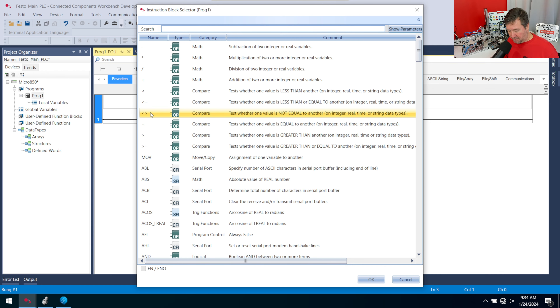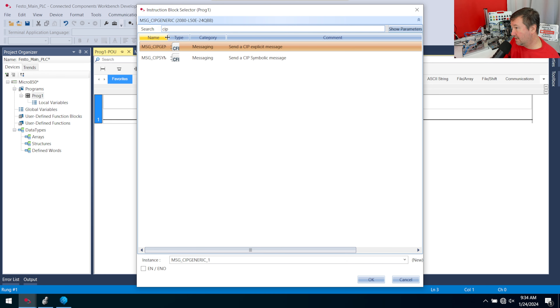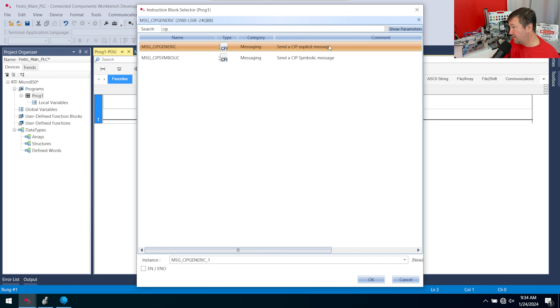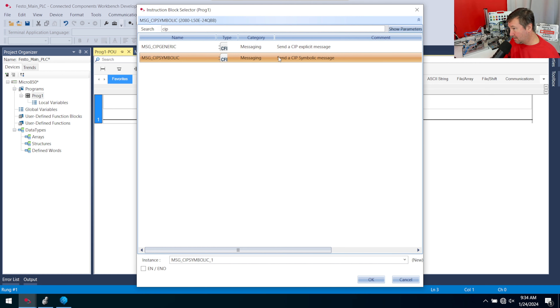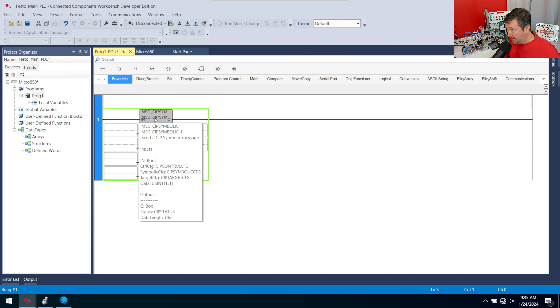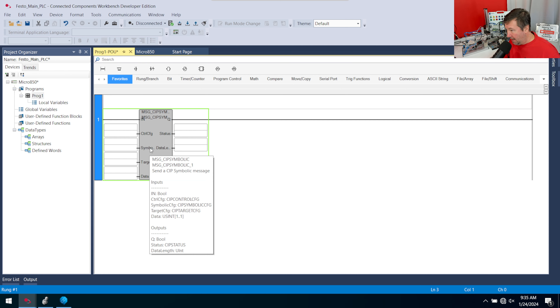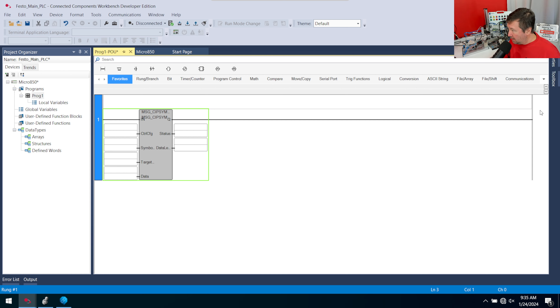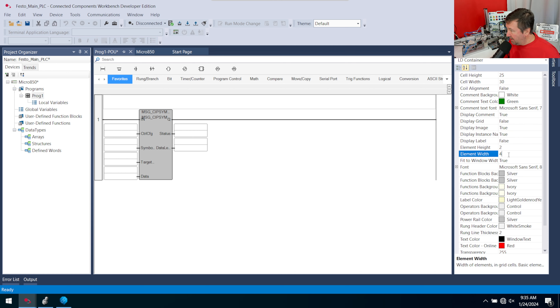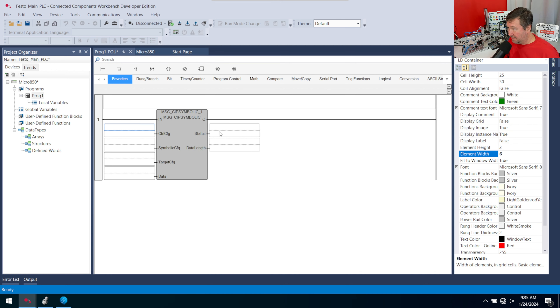This time we're doing CIP messaging. If you type CIP in the instruction search, you get two options: CIP Explicit Message, which exposes class, instance, and assembly details; and the CIP Symbolic Message, which is easier to use when communicating natively between compatible devices. Right-click to the right of your ladder, go to Properties, and change the element width to 6 so we can read the full parameter names.